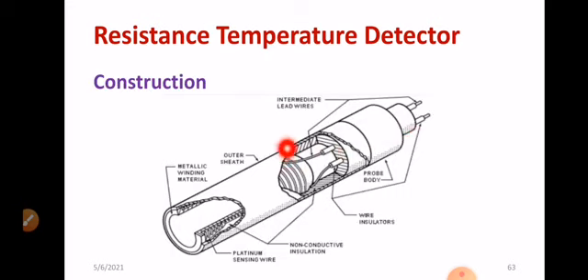You can see the construction details of the R.T.D. We have the lead wire, the intermediate lead wire, which is used for calibration, and we have the probe body. Inside you can see the platinum wire. Platinum wire can be seen inside. It is very clear, and the metallic winding material is also there at the bottom edge. This is the outer sheath for protection against mechanical injury, and we can see the platinum sensing wire also. At the bottom side you can observe the platinum sensing wire, and non-conductive insulation is also available here. It is very clearly observable. So this is the basic construction detail of a resistance temperature detector.